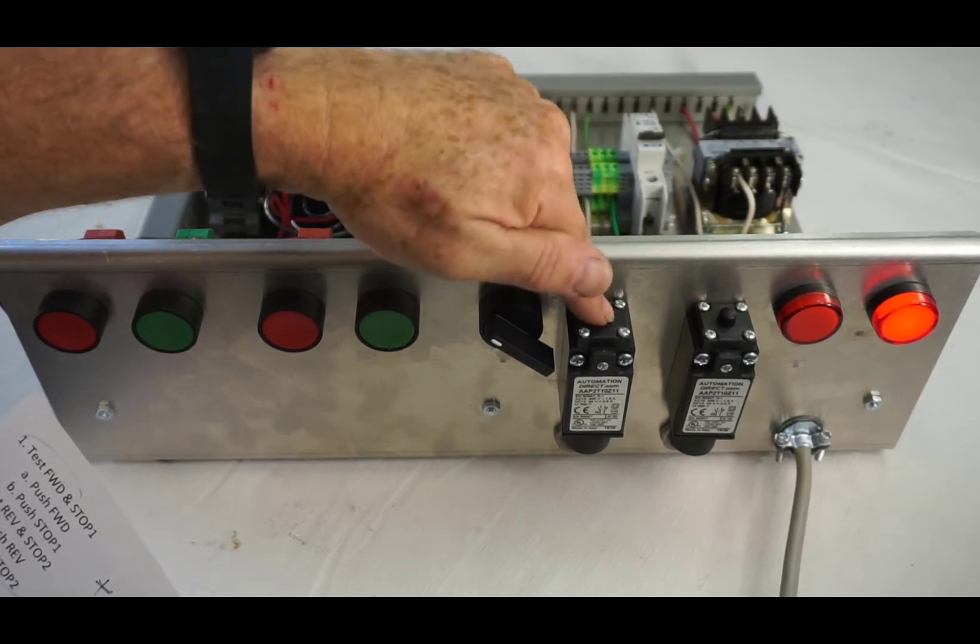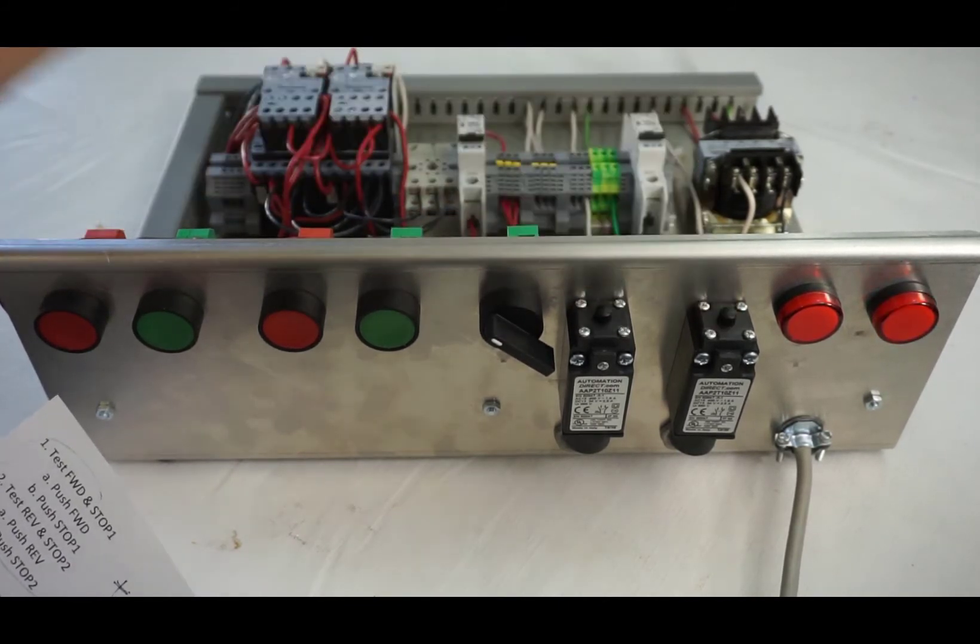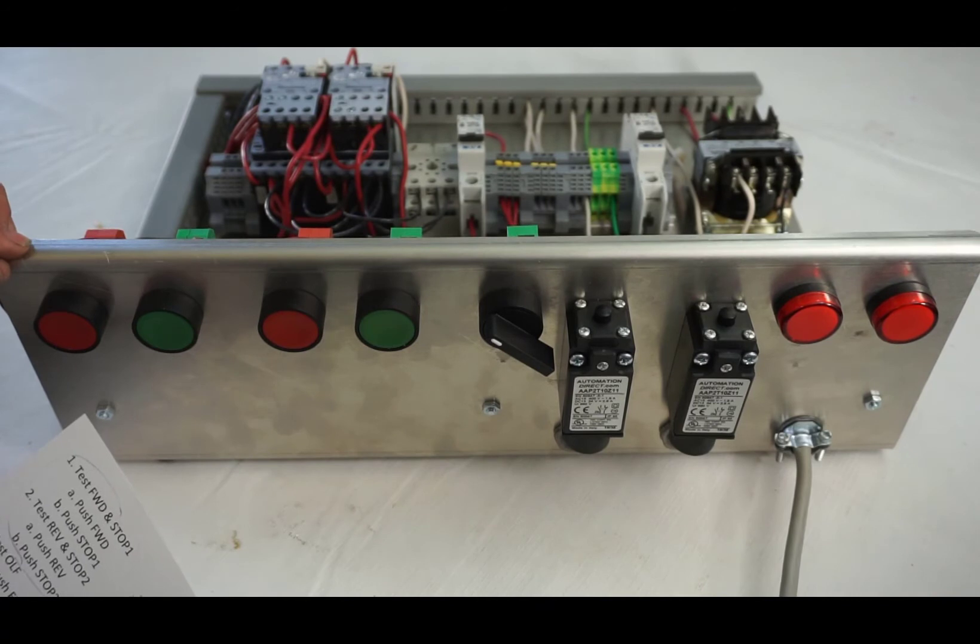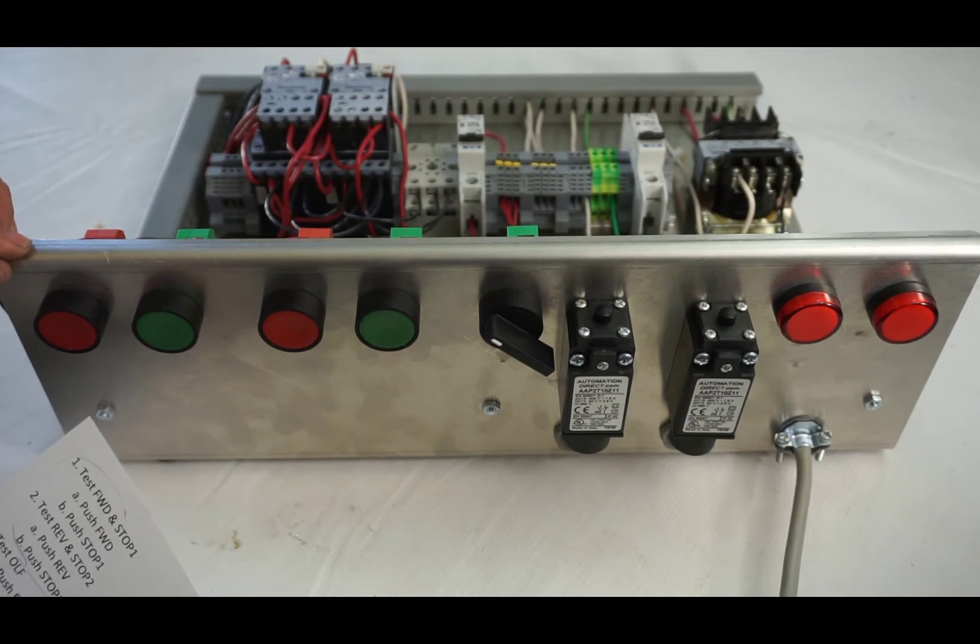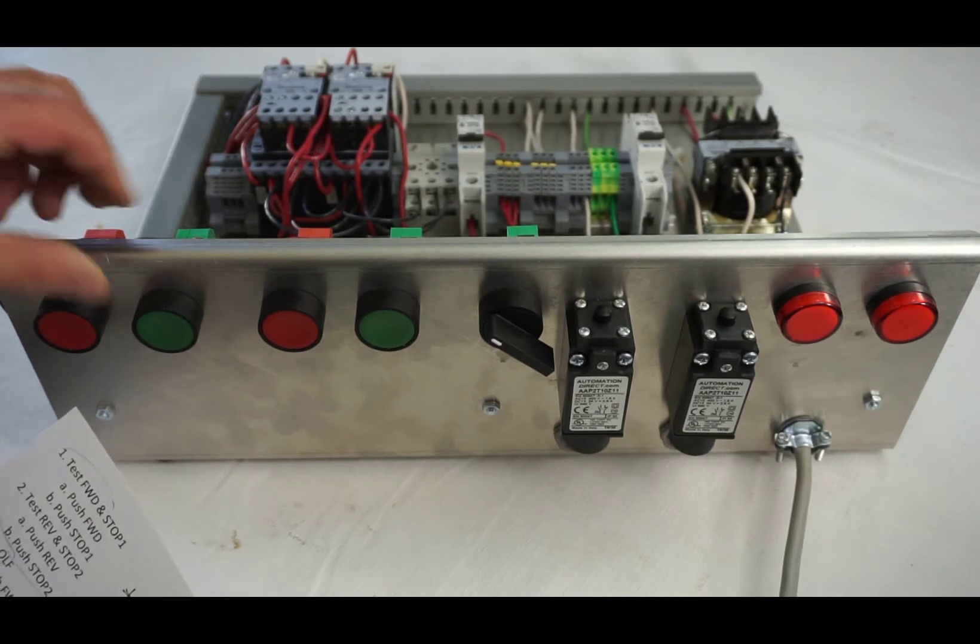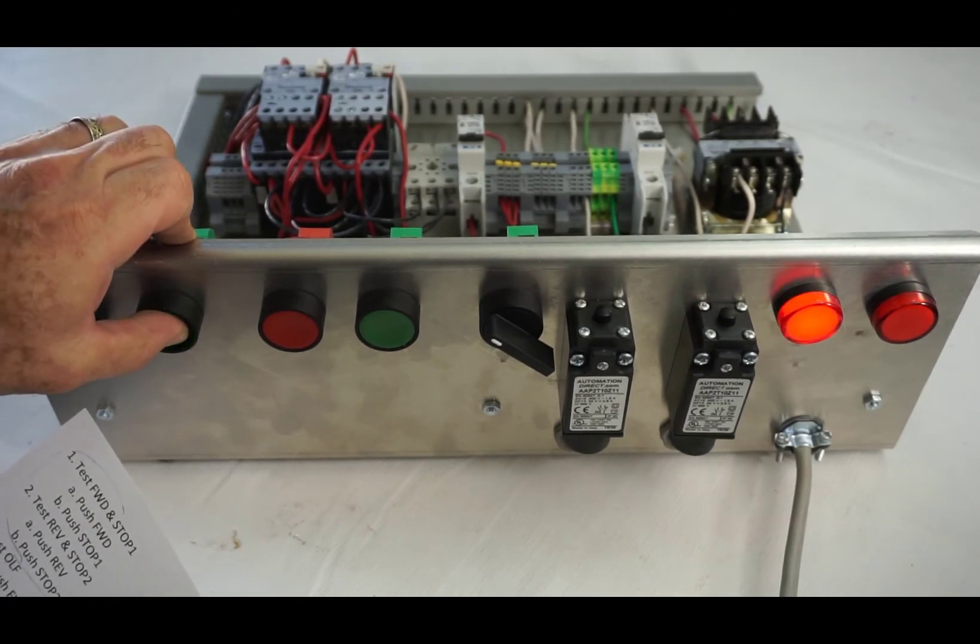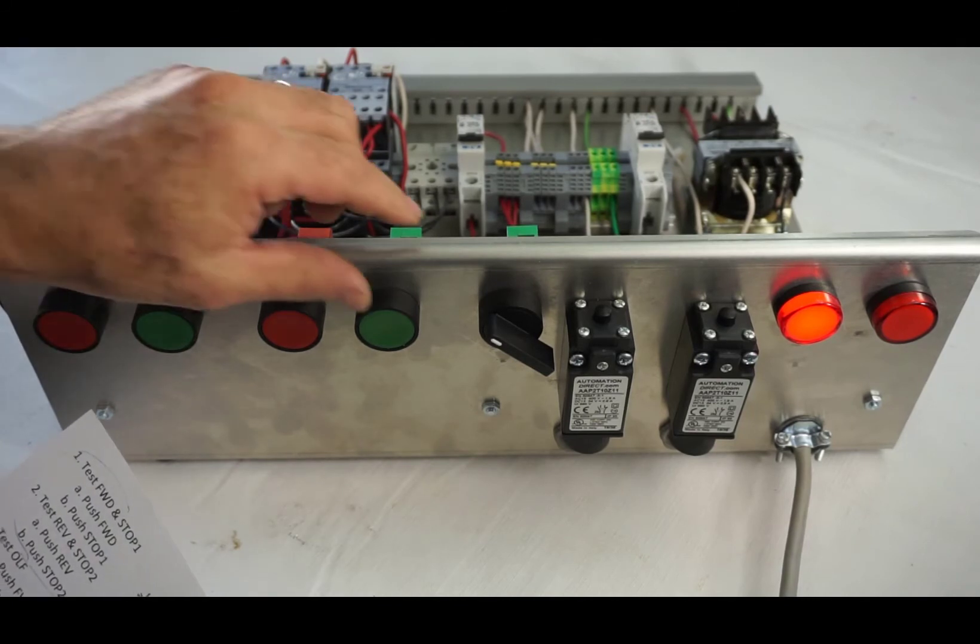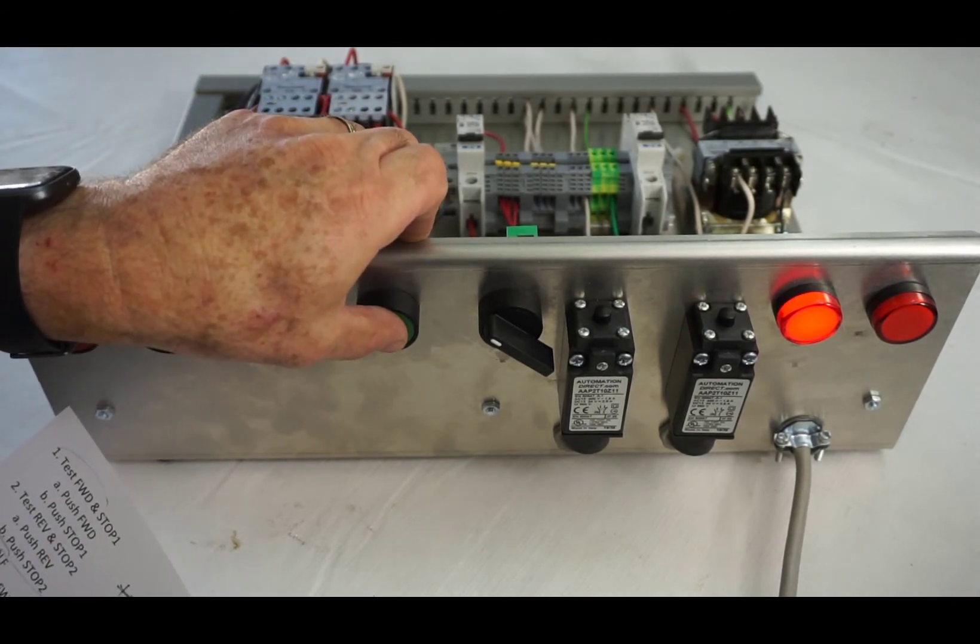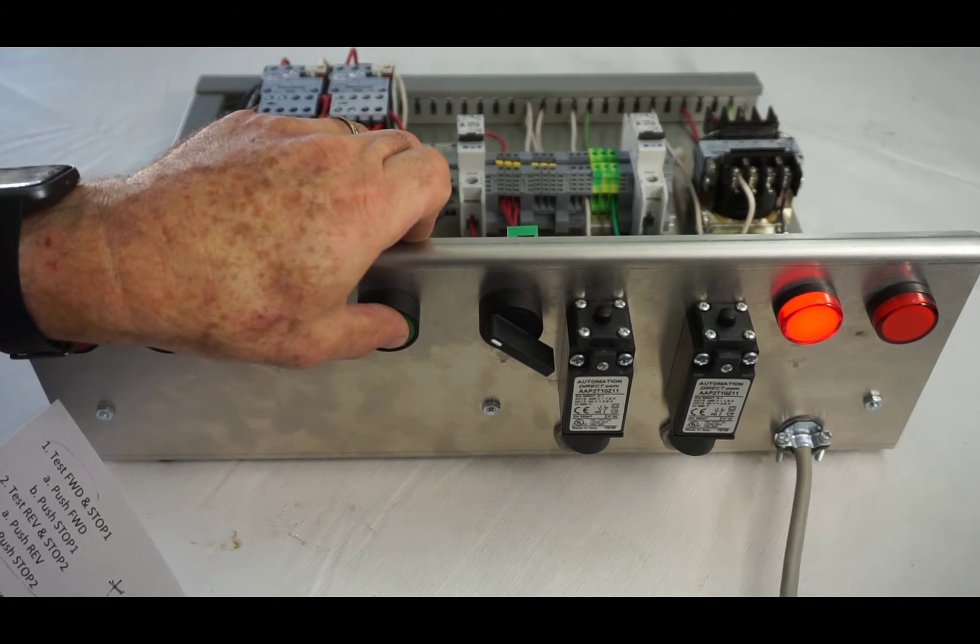Alright, now we're going to test the forward interlocks. Push forward. Now I'm going to push reverse and I got to listen to see if I hear anything, any kind of chattering or anything. Dead quiet, so we're good.